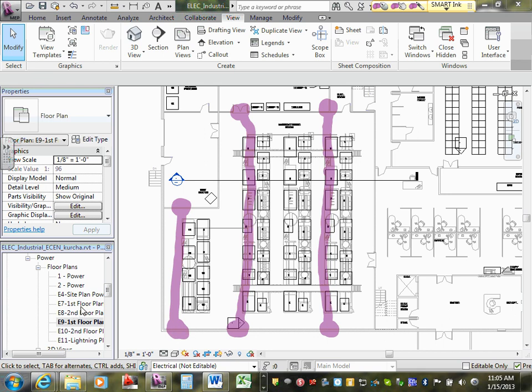In an area like this, if they were really worried about it, I'd recommend the Vesda system, just because it's air sampling, it's a pipe, and it's easier to test, you're not going to damage it. If they do have the trolley and everything going across here, cranes, whatever, it can always put these into alarm or put them into trouble. If they don't see their signal, they're either going to go into alarm or trouble. One of the other new technologies coming out, through Xtralis, is called an OSID. It's one transmitter, and you can have up to 7 video receivers from one transmitter, and it constantly sends out to all of them.